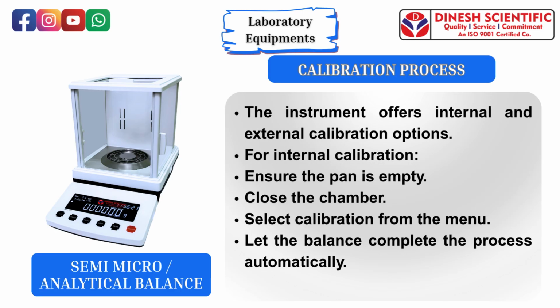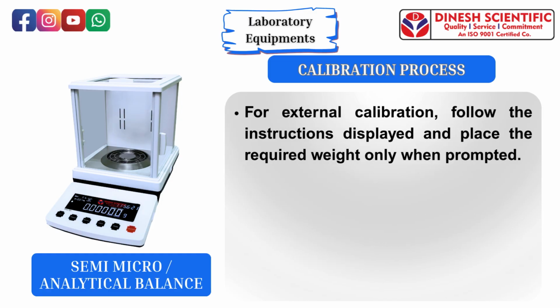Calibration process. The instrument offers internal and external calibration options. For internal calibration, ensure the pan is empty. Close the chamber. Select calibration from the menu. Let the balance complete the process automatically. For external calibration, follow the instructions displayed and place the required weight only when prompted.